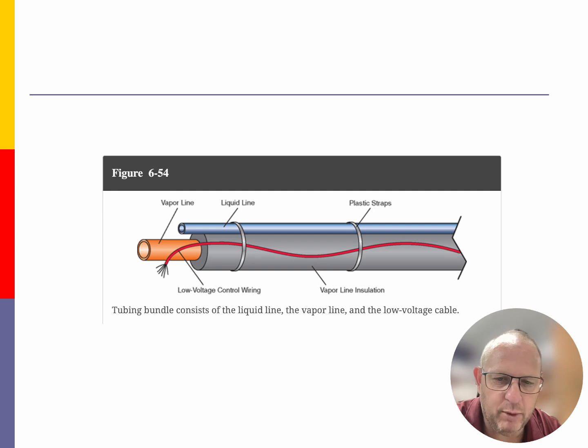So I like the picture. I like the way that they're depicting how you should run that particular unit. Take a look that we are wrapping both the communication wire, the low voltage, not the high voltage, the liquid line and the suction line, and we're bundling them together to run them from one location to another, from the outdoor unit to where the indoor unit actually is. So that's going to be nice.